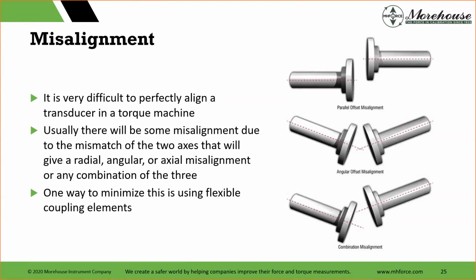So here, misalignment. Here are some examples of misalignment. You're trying to line everything up. It's almost impossible. No system is perfect. So it's not uncommon for the errors from misalignment to raise the combined uncertainty by more than 10%. That's a huge number. That's like you're really getting things wrong. But would you know? The question is, would you know if you had that error unless you're sending a cell to PTB, sending a cell to Morehouse, and bringing it back and doing your own ILC? That's a hard one. A lot of people don't close the loop. They just say, I have this known force, I have this known length, I'm good. That's not the case, and we're going to show you more examples of that.